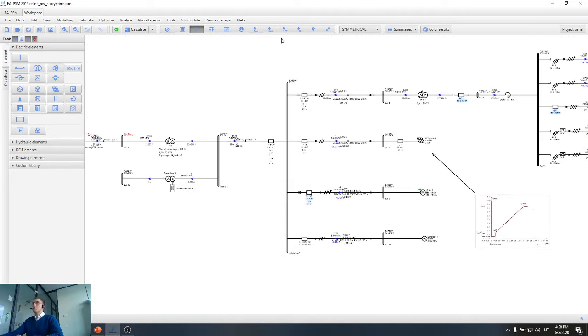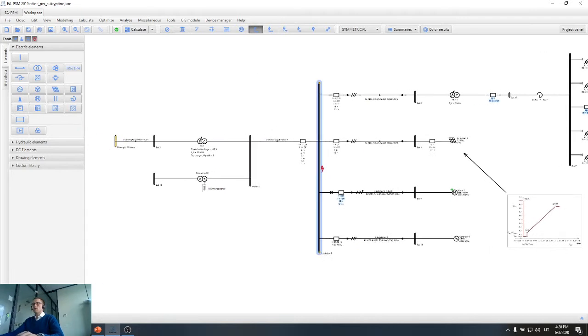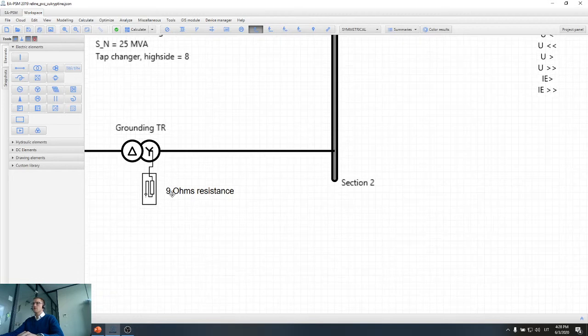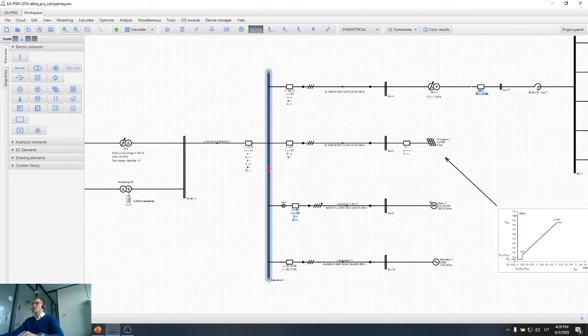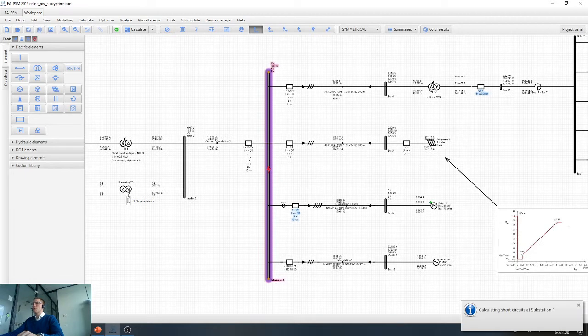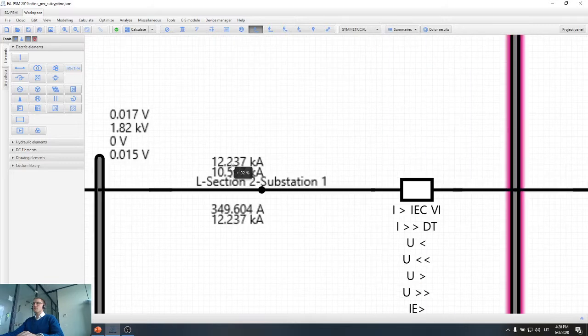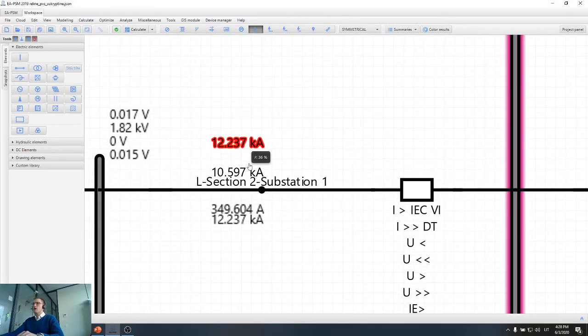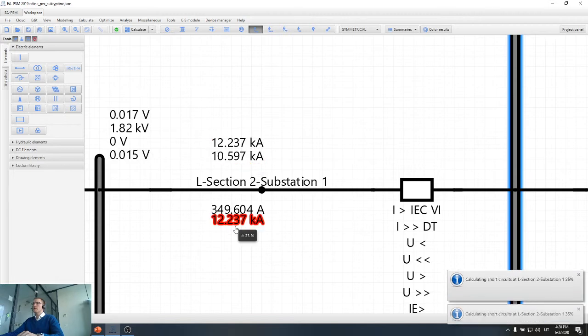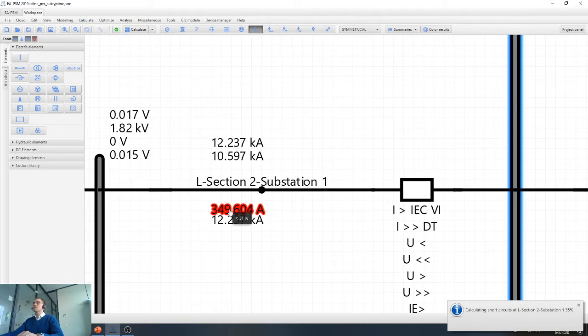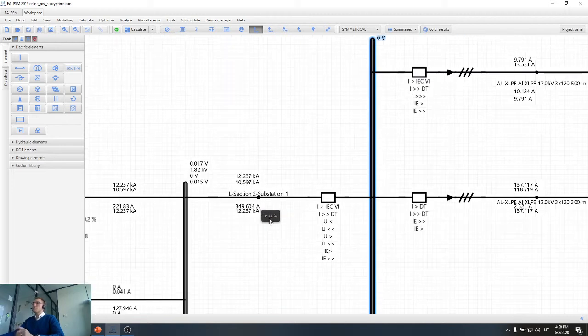Let's go further on. In this kind of network, as I have mentioned, we have smaller earth fault current because we have resistance grounding. So let's calculate the short circuit at the bus bar here. We can see that the 3-phase short circuit current is over 12,000 amps, 2-phase is 10,000 amps, and the 1-phase short circuit current is 349 amps. So you can see that the 1-phase short circuit current is much smaller. Therefore we need a different kind of protection device in order to protect the network from this 1-phase short circuit current, and this kind of protection device can be ground fault protection.